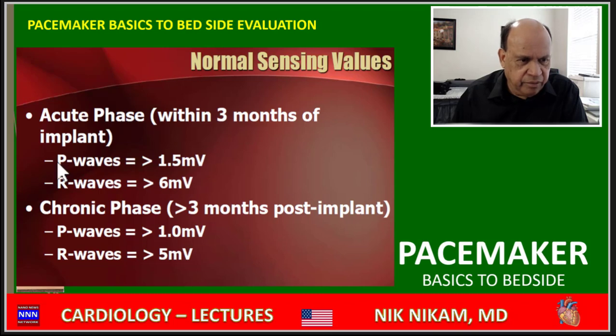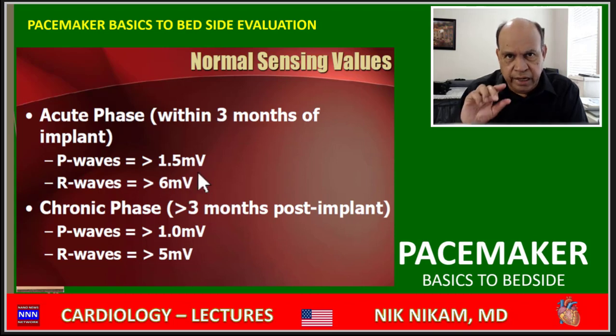The usual P wave sensitivity is set to 1.5 in the first 3 months, and as the electrode gets more established, the sensitivity drops to 1.0 millivolts. That means it can recognize P waves with an amplitude of 1 millivolt, and when it sees that, it suppresses the atrial lead from creating a beat.